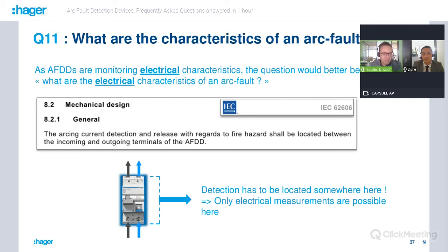And just to explain why we have to use electrical characteristics: in the standard, there is a sentence which says the arcing current detection and release with regards to fire hazard shall be located between the incoming and the outgoing terminals of the AFDD. It means the detection has to be located somewhere here. So we cannot use other physical values like sound or temperature. The only thing we can use are the electric signals which are coming through the AFDD.